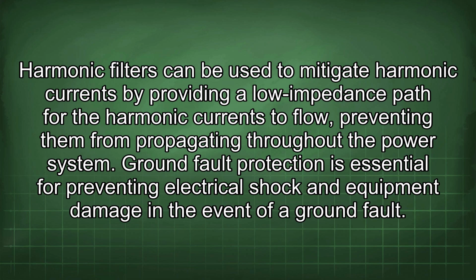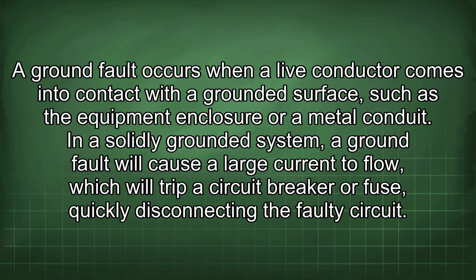preventing them from propagating throughout the power system. Ground fault protection is essential for preventing electrical shock and equipment damage in the event of a ground fault. A ground fault occurs when a live conductor comes into contact with the grounded surface, such as the equipment enclosure or a metal conduit. In a solidly grounded system, a ground fault will cause a large current to flow, which will trip a circuit breaker or fuse, quickly disconnecting the faulty circuit.